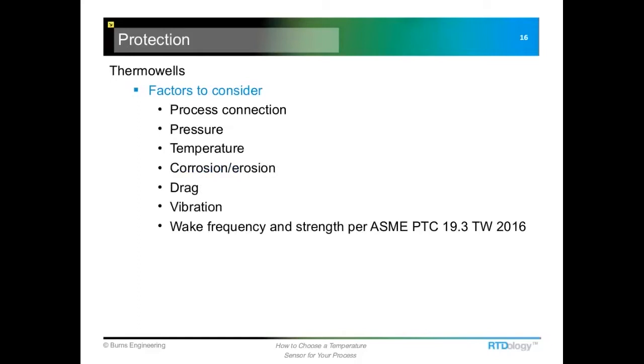So when we're selecting a thermal well, we have quite a few things to look at. Again, the wake frequency is going to be one of the more important things, and we have to look at how we are going to attach it to the piping, pressure rating, temperature, and whether there's going to be any corrosion or erosion. Is the pipeline vibrating? Things like that. In our process, we have just water, so we really don't have to be too concerned about corrosion or erosion of the thermal well, and the wake frequency and strength calculations are going to take care of our issues with drag on the thermal well due to the flow rate.